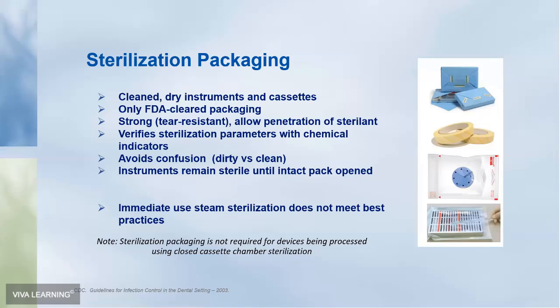The other thing that sterilization packaging does is it verifies your sterilization parameters by using chemical indicators. So the parameters are time, temperature, and pressure. The critical ones are time and temperature. Pressure is the third one. So those parameters, the chemical indicators, will let you know if it reached that parameter. Now, since the chemical indicators change physically, it also avoids confusion between dirty and clean instruments, because they're within this packaging with the chemical indicators. The instruments will remain sterile in the packaging as long as the packaging is intact and until it's opened.